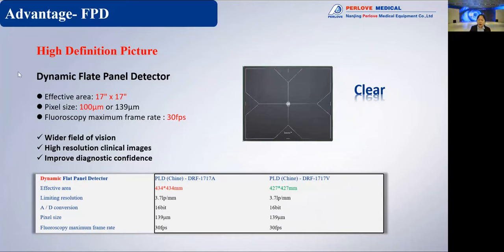I want to emphasize its pixel size can be up to 100 micron. As I mentioned, 100 is the top level now. Under fluoroscopy mode, the frame rate can be up to 30. That means in 1 second observation for the structure, we collect 30 images. So this machine reduces the possibility of misdiagnosis very well, on a large scale. The dynamic flat panel detector can bring us clear images and an excellent diagnostic experience.